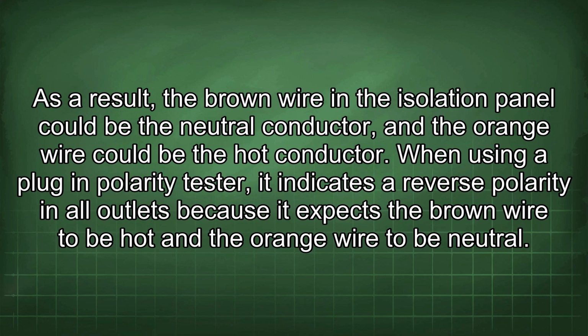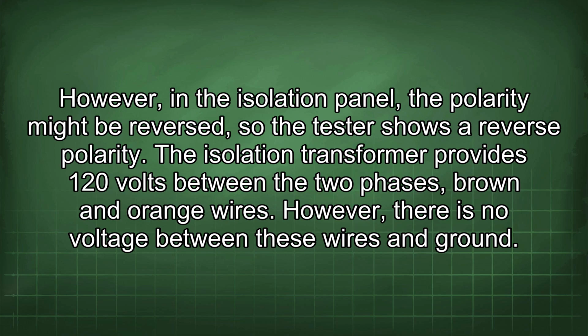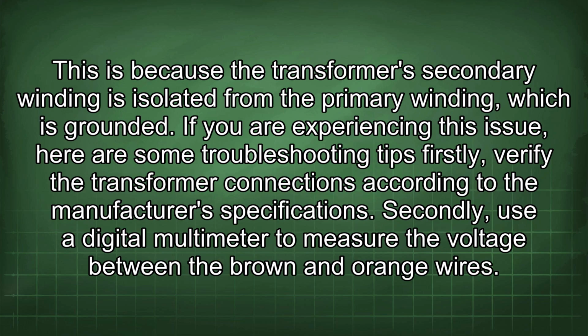be the hot conductor. When using a plug-in polarity tester, it indicates a reverse polarity in all outlets because it expects the brown wire to be hot and the orange wire to be neutral. However, in the isolation panel, the polarity might be reversed, so the tester shows a reverse polarity. The isolation transformer provides 120 volts between the two phases, brown and orange wires. However, there is no voltage between these wires and ground. This is because the transformer's secondary winding is isolated from the primary winding, which is grounded.